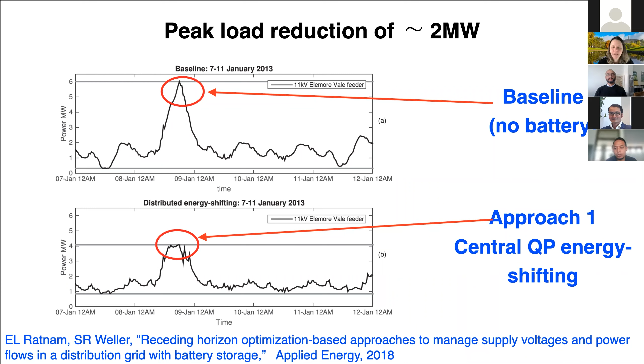Does fixing the central problem also fix the local voltage issue? For this feeder, supply voltages must stay within plus 10% and minus 6% of the nominal 230 volts, which is the standard nominal voltage on Australia's east coast. Previously we looked at scheduling everyone's batteries in the same way to reduce peak load, but what does that solution do to supply voltages?